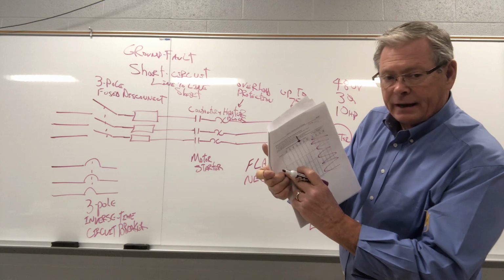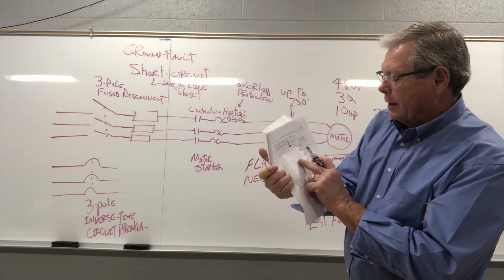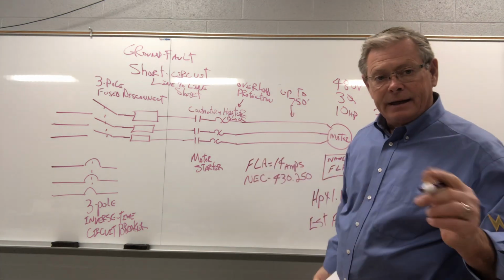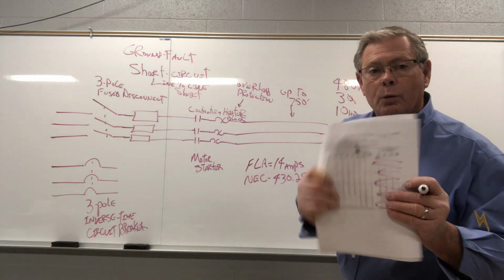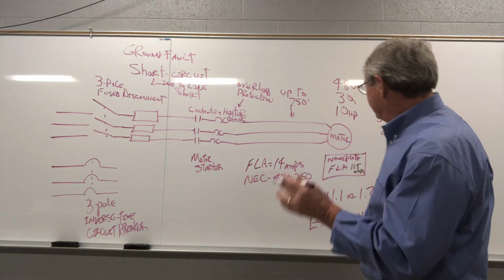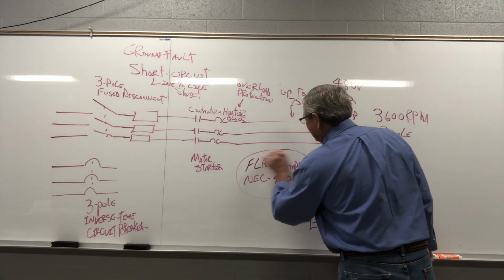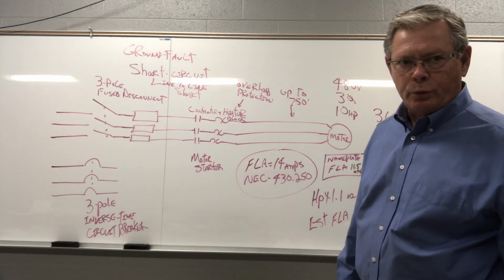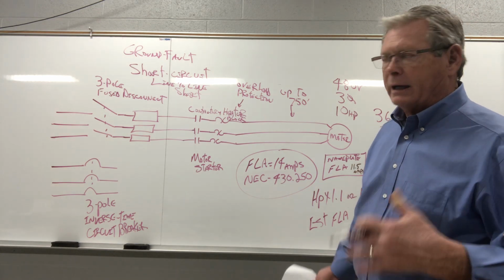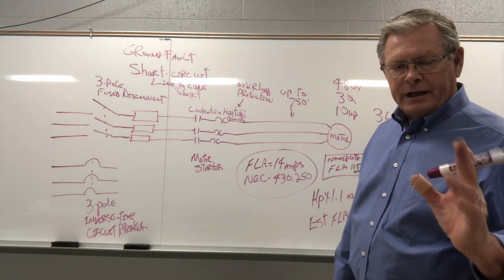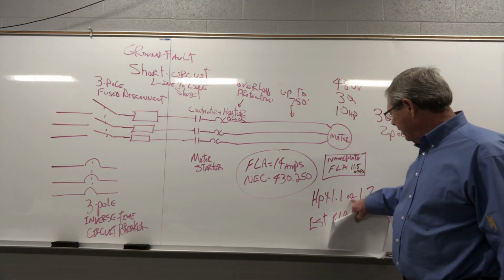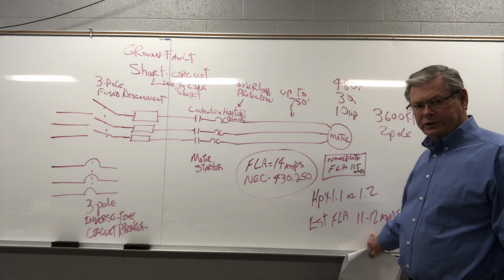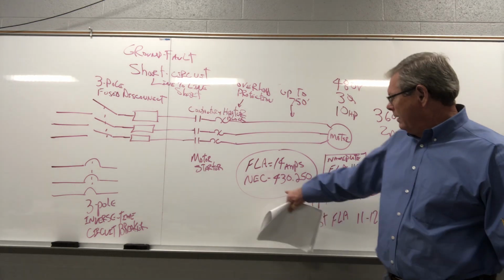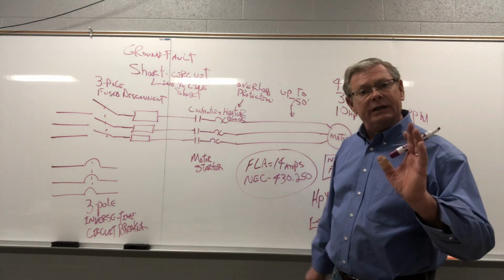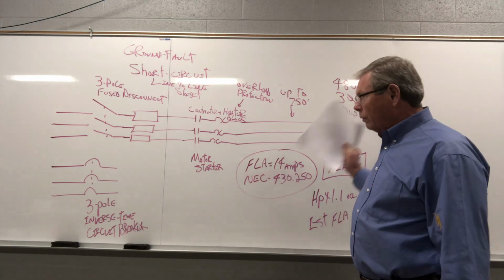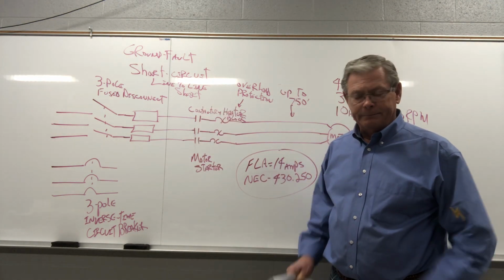We go over here and come down to 10 horsepower, come across to 460, and it tells us the worst case, this is the worst case full load current. So it tells us that it's going to be 14 amps. We're going to build this circuit, you might say hell for stout, so that it'll take any 10 horse motor. Now, this here, if we multiply 1.1 and 1.2, we're seeing 11 to 12 amps full load. The table says 14, so see the table's going to be a little higher. So we're building this circuit so it'll last forever.